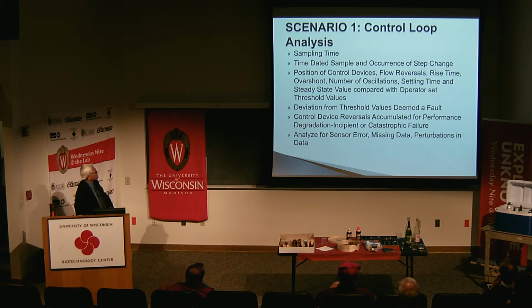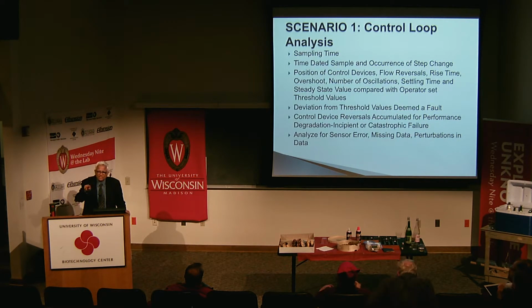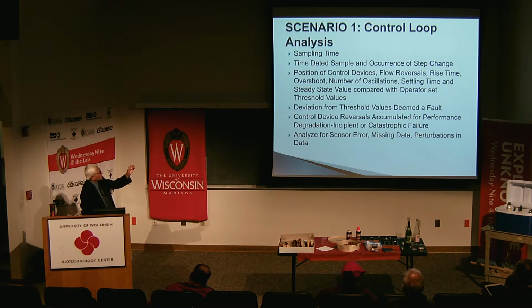Now, control loop analysis. Here you have to know the sampling time. In the control loop, depending upon whether it's a fast loop or a slow reacting loop, for fast loops you normally sample every 5 seconds because you have to make sure they reach the set point within a reasonable amount of time. And you time and date the sample and occurrence of step change. When I say step change, for example, if you take a cooling coil, the air coming in, if the outdoor weather conditions change, the mixed air conditions, you may have a step change in the outdoor air temperature or the latent load, or the leaving temperature, you may reset it to a higher level.